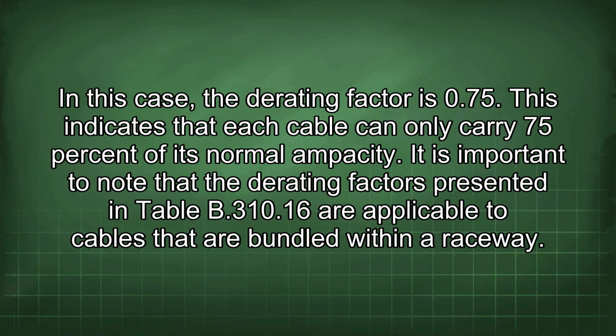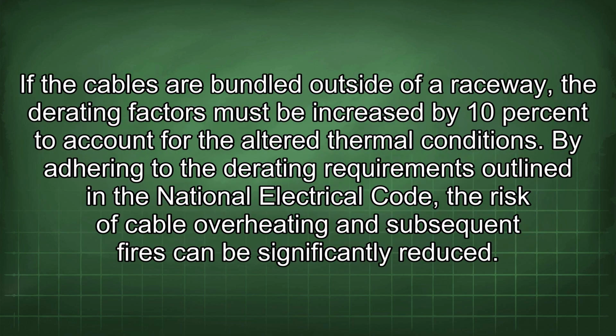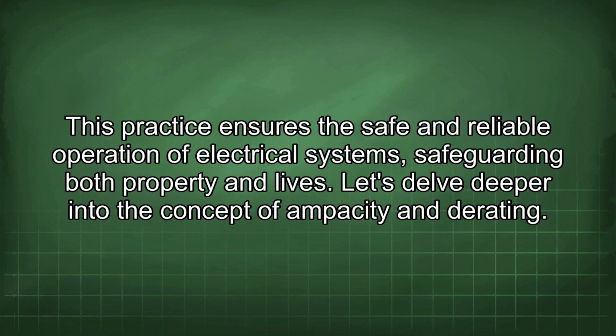It is important to note that the derating factors presented in Table B 310.16 are applicable to cables that are bundled within a raceway. If the cables are bundled outside of a raceway, the derating factors must be increased by 10% to account for the altered thermal conditions. By adhering to the derating requirements outlined in the National Electrical Code, the risk of cable overheating and subsequent fires can be significantly reduced. This practice ensures the safe and reliable operation of electrical systems, safeguarding both property and lives.